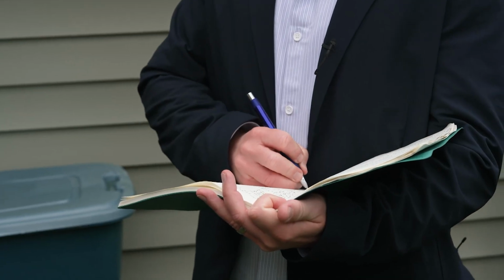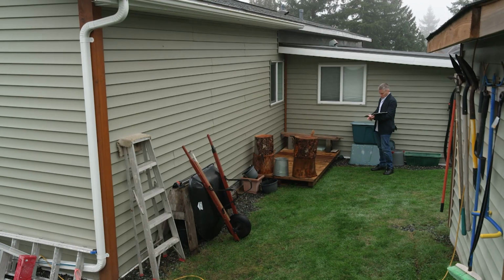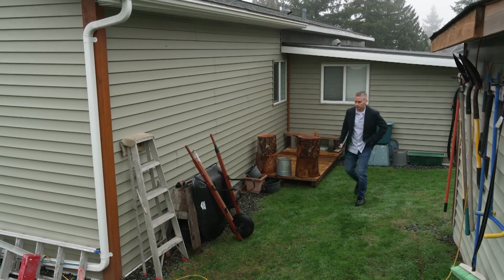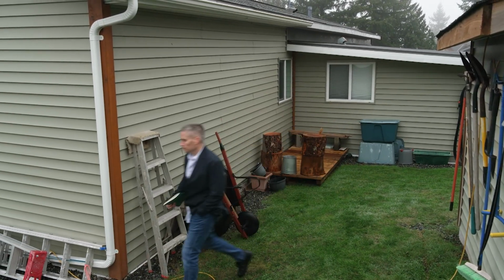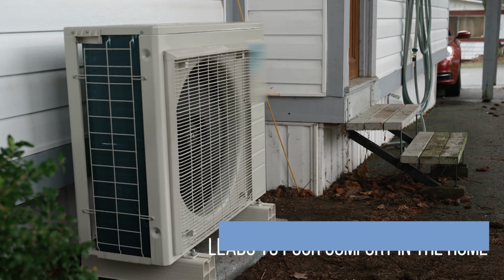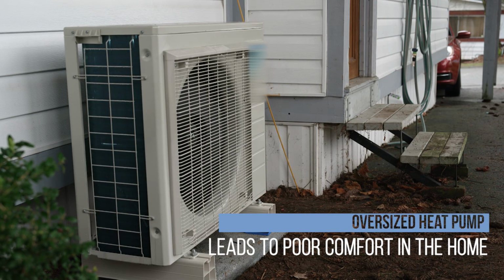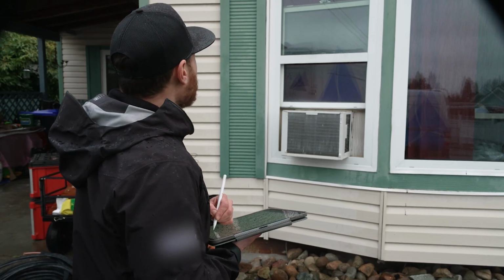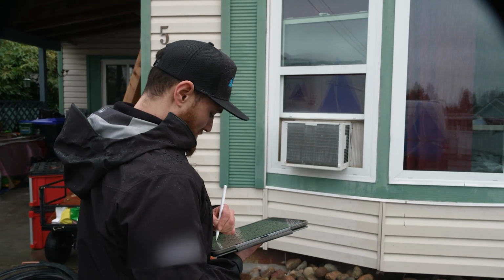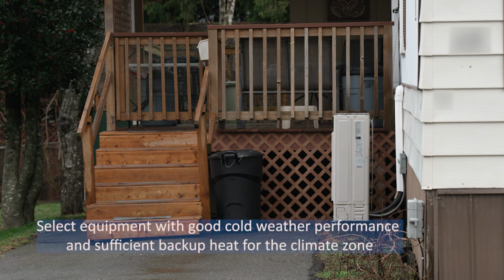Often manufactured homes have been upgraded throughout the years with add-ons and modifications, which means rule of thumb calculations are even less accurate than usual. A common mistake is oversizing the heat pump, which leads to short cycling, uneven heating, and more cost. You get the correct equipment size by doing heat loss calculations for the home. Choose a system with good cold weather performance and sufficient supplementary or backup heat.